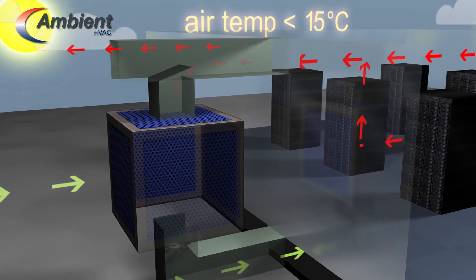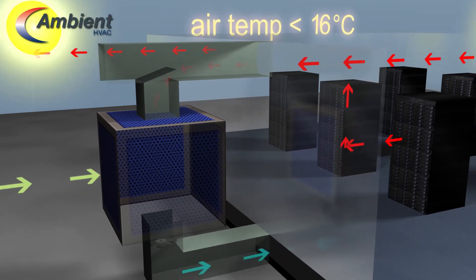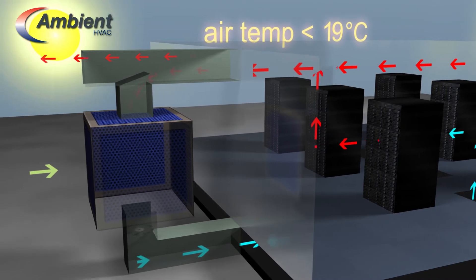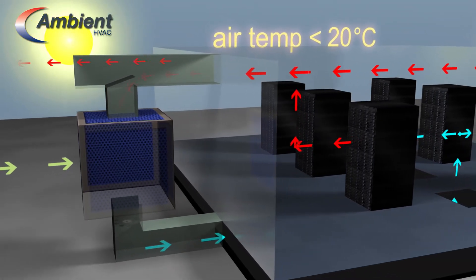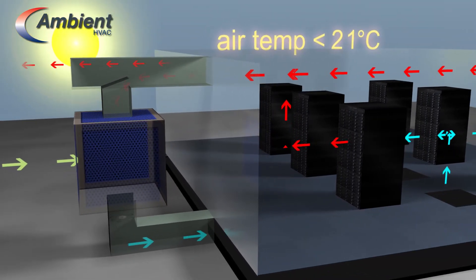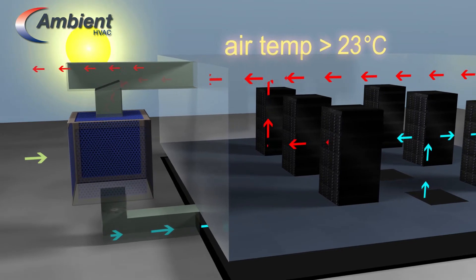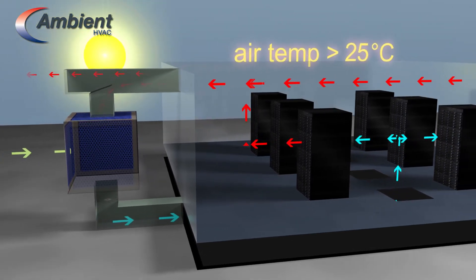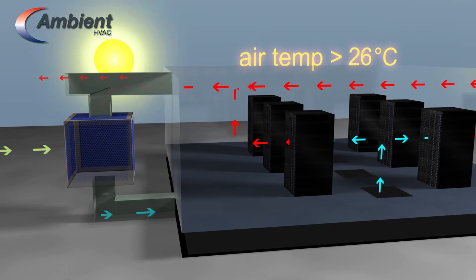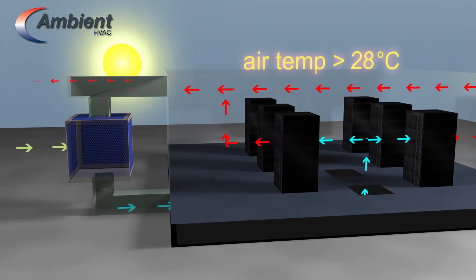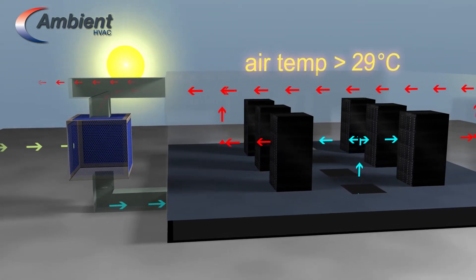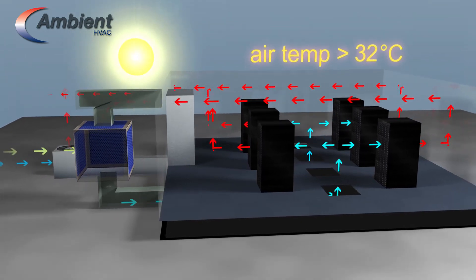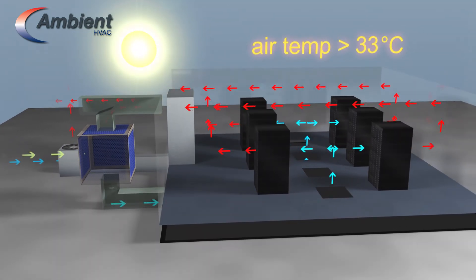As ambient temperatures continue to rise further, evaporative cooling is enabled. Mains water is pumped to the top of the evaporating unit and recirculated over water absorbent pads. Introduced air is cooled by the evaporative effect as it is drawn over them. Humidity can be accurately controlled. A CRAC can provide backup if ambient temperatures continue to rise further.